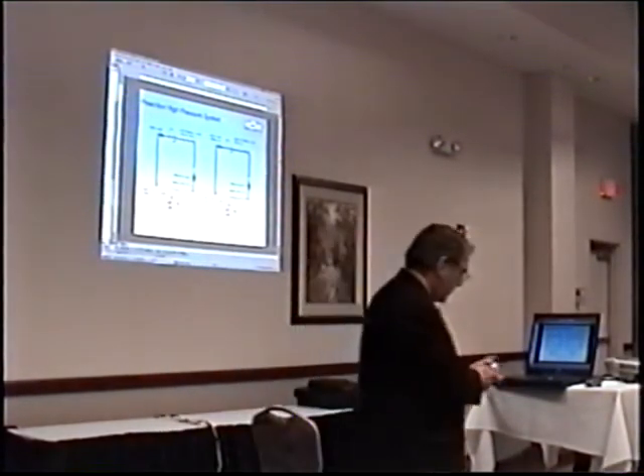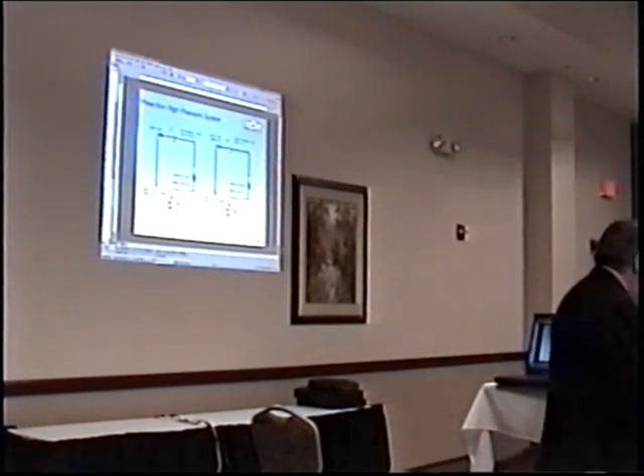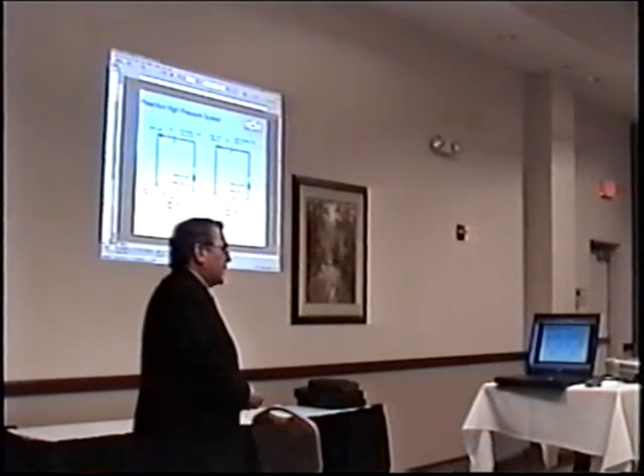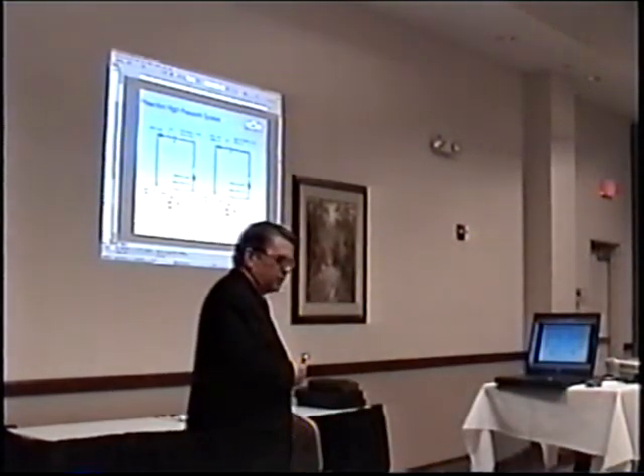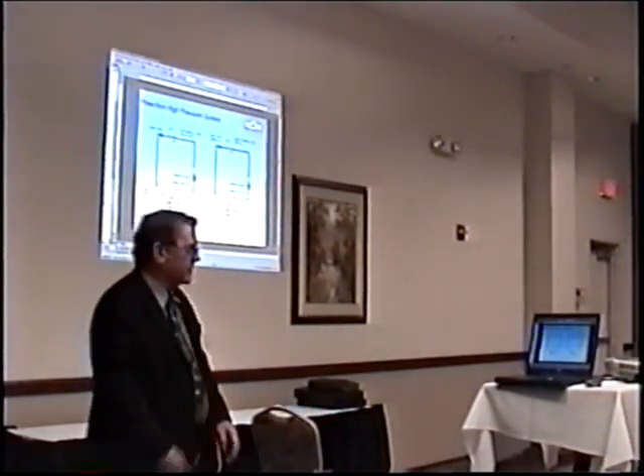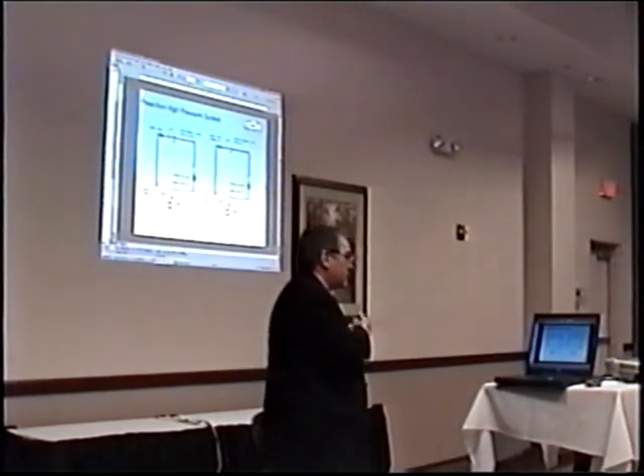I have additional nozzles here if you're interested. This is one from Kidde Deugra, Germany, and I used that system and that nozzle. They tested that nozzle in some fire tests I did in New Zealand in the electrical tunnel, and that has extremely fine, almost like horsehair diameter orifices. Extremely fine orifices, very low flow rate, very nice atomization, and it did better than any other nozzles tested in those fire tests in terms of meeting the temperature control requirements.